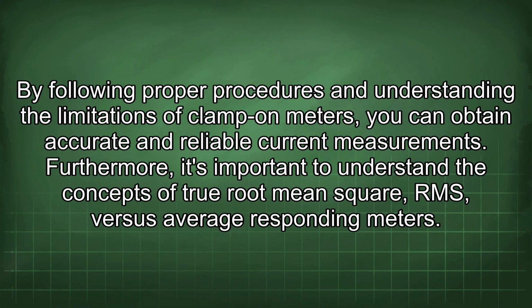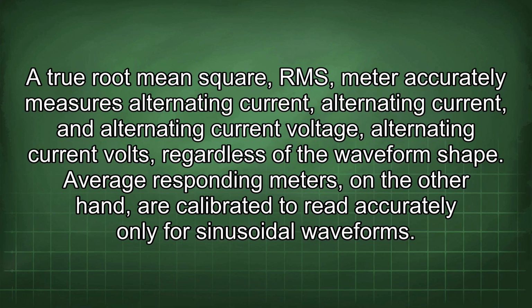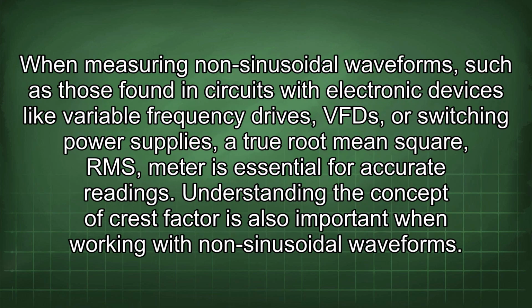Furthermore, it's important to understand the concepts of true root mean square (RMS) versus average responding meters. A true RMS meter accurately measures alternating current and alternating current voltage, regardless of the waveform shape. Average responding meters, on the other hand, are calibrated to read accurately only for sinusoidal waveforms. When measuring non-sinusoidal waveforms, such as those found in circuits with electronic devices like variable frequency drives (VFDs) or switching power supplies, a true RMS meter is essential for accurate readings.